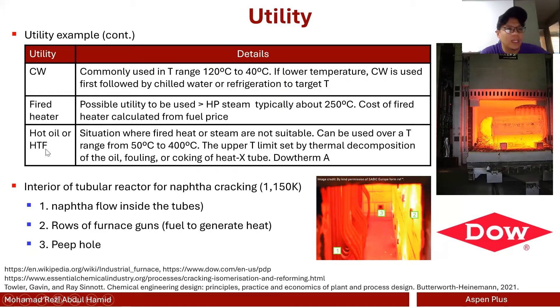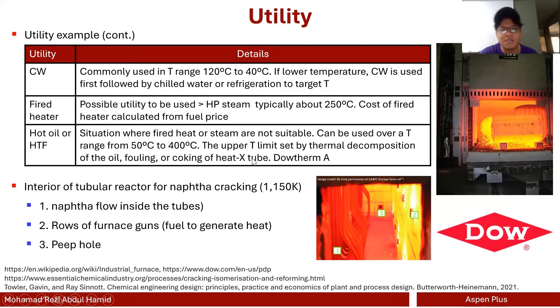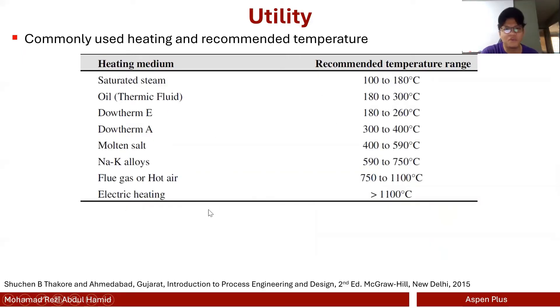We also have hot oil, or heat transfer fluid — for example, Dowtherm A, produced by Dow Chemicals. This is good for when a fired heater or steam are not suitable. For example, at the company I worked at previously, we dealt with bitumen, so we used hot oil as a heat transfer element to make sure the bitumen was always above its pour point so it could be pumped and transported more easily. The temperature range is between 50 to 400 degrees Celsius, with the upper limit set by the thermal decomposition of the oil itself.